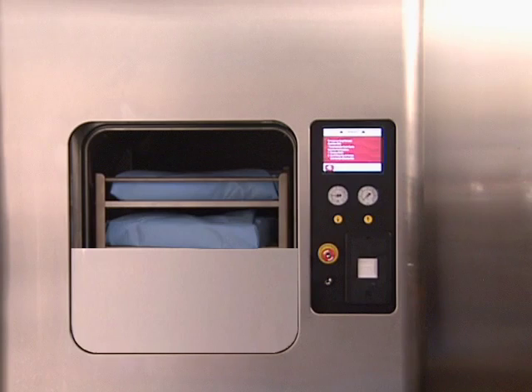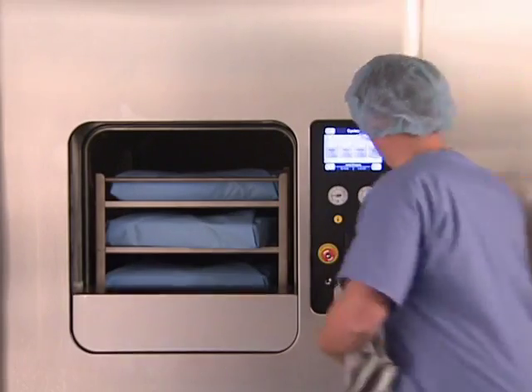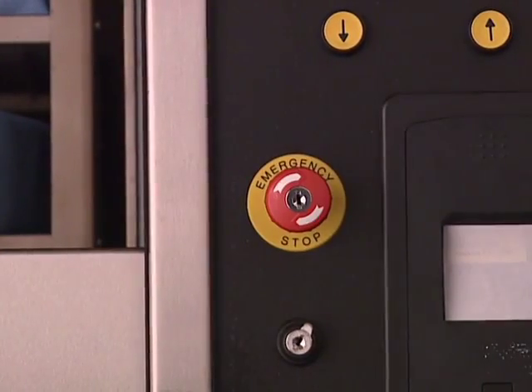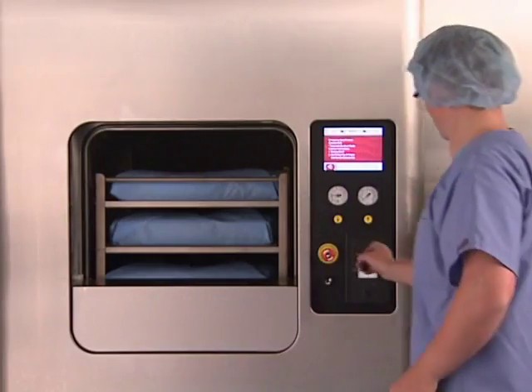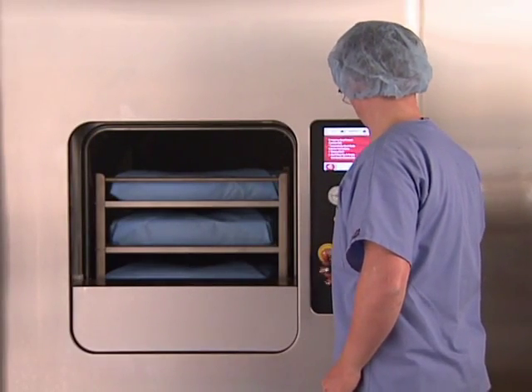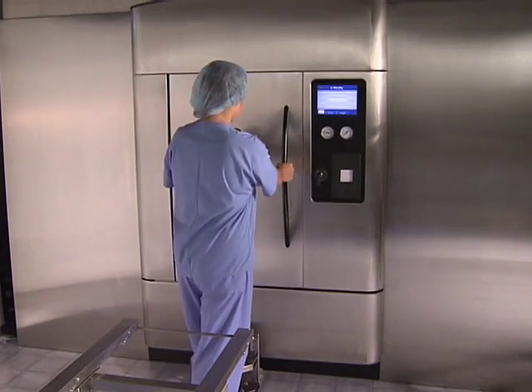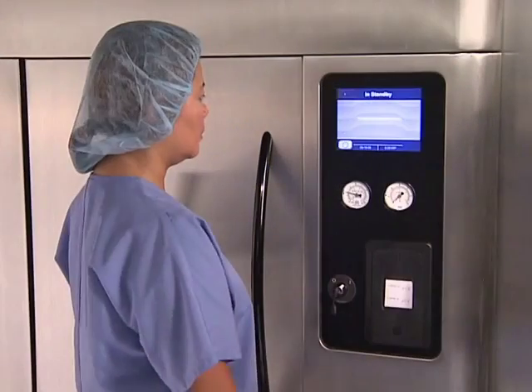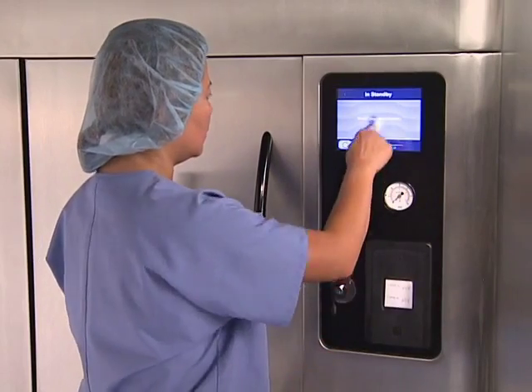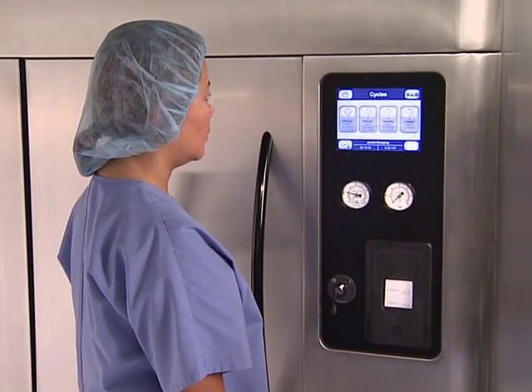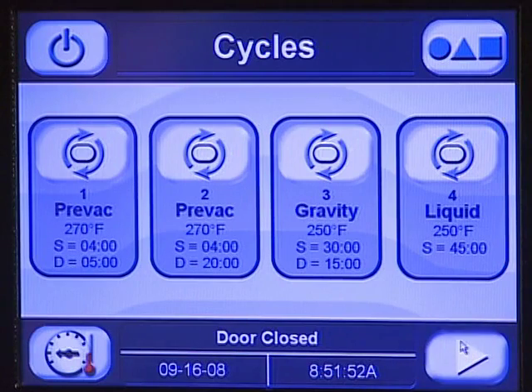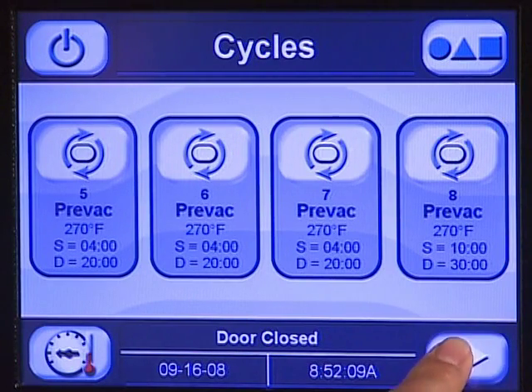Sterilizers with automated doors will stop automatically if obstructed. If this happens, remove the obstruction, then close the door. If you notice the obstruction before the door stops, you can press the emergency stop button to shut off all outputs on the sterilizer. Then reset the switch with the key. Now you're ready to run a cycle. If the sterilizer is in standby mode, press anywhere on the standby screen to bring up the control display. Cycles are started from the cycle selection screen.